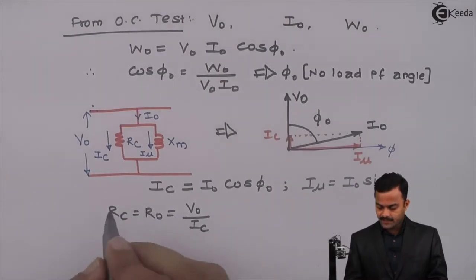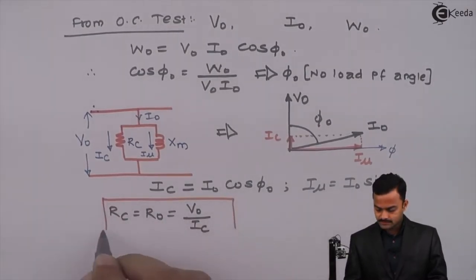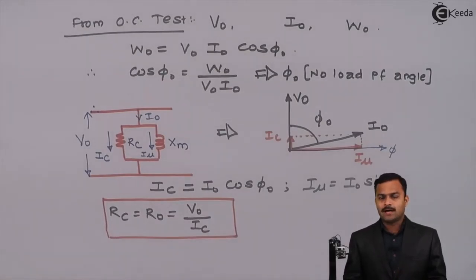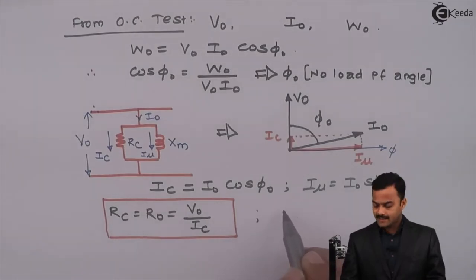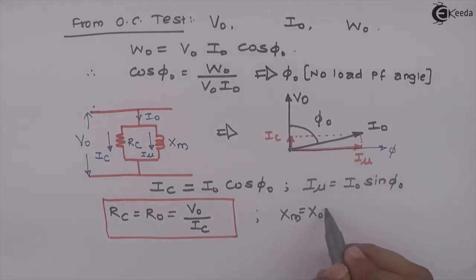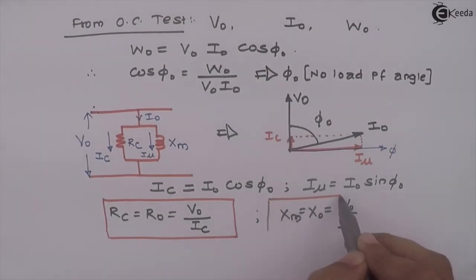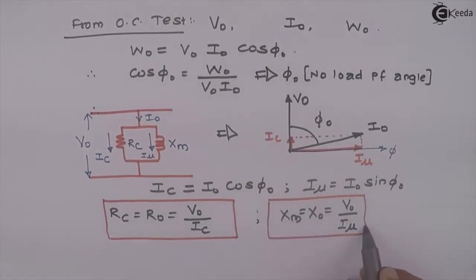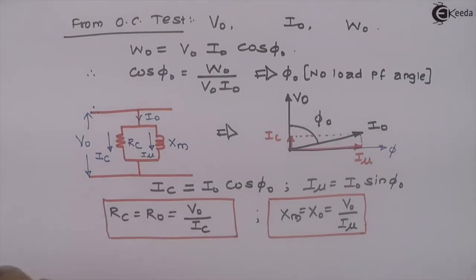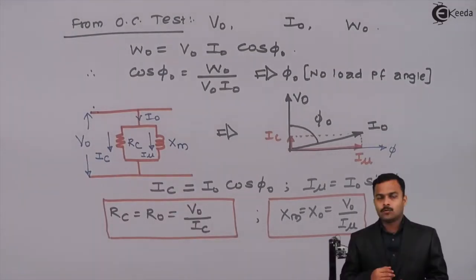From these two values we can get RC, also called no-load resistance R0, which equals V0 divided by IC. Similarly, magnetizing reactance Xm, also called no-load reactance X0, equals V0 divided by Iμ. These two parameters — RC and Xm — are the outcome of the OC test, along with the core losses measured by the wattmeter.